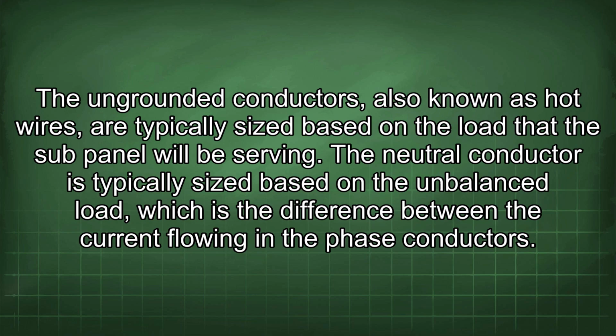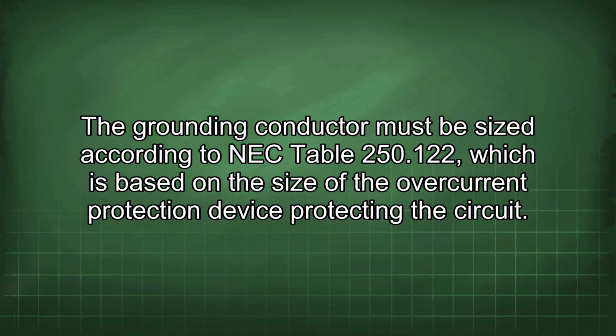The ungrounded conductors, also known as hot wires, are typically sized based on the load that the sub-panel will be serving. The neutral conductor is typically sized based on the unbalanced load, which is the difference between the current flowing in the phase conductors. The grounding conductor must be sized according to NEC Table 250.122, which is based on the size of the overcurrent protection device protecting the circuit.